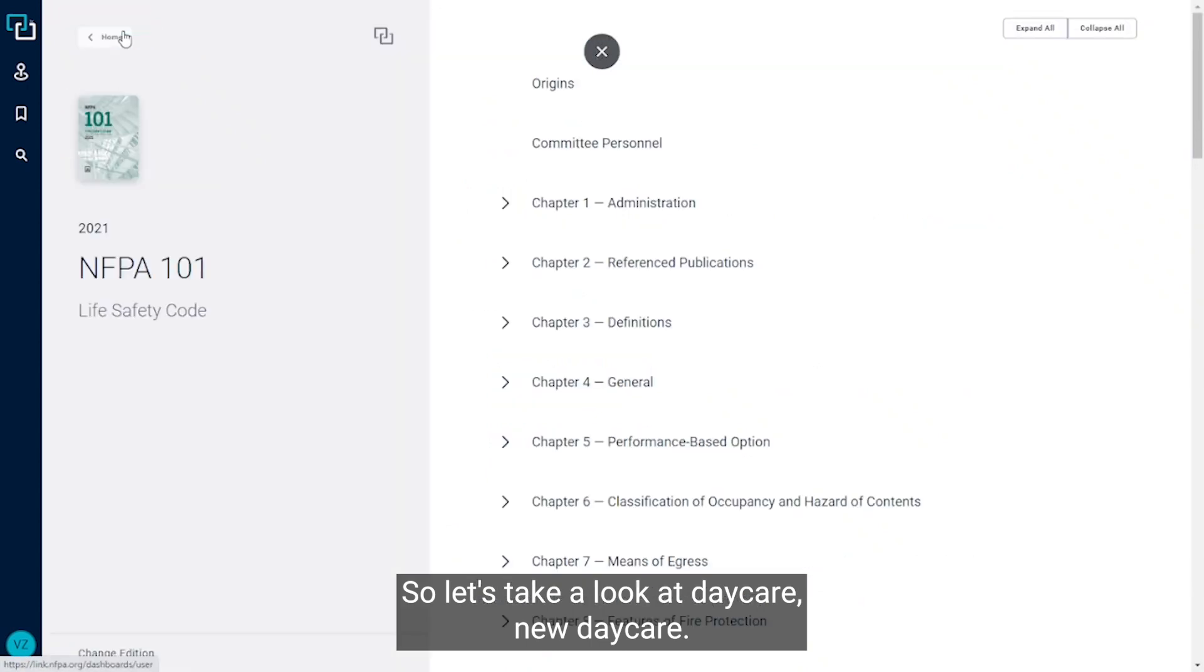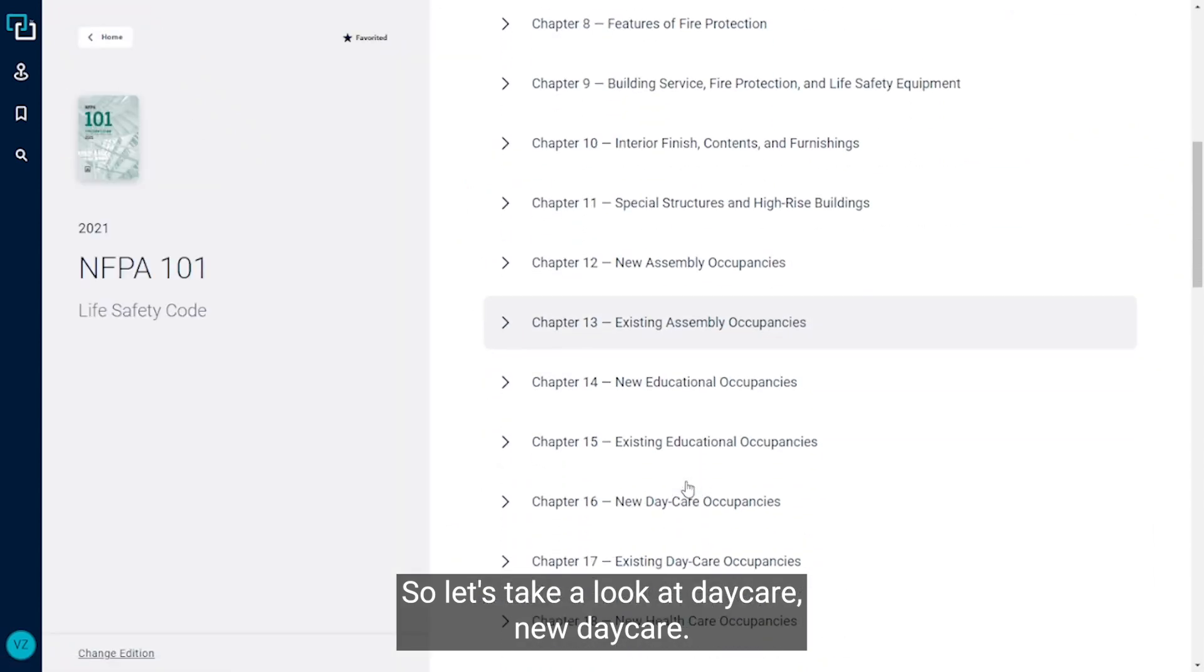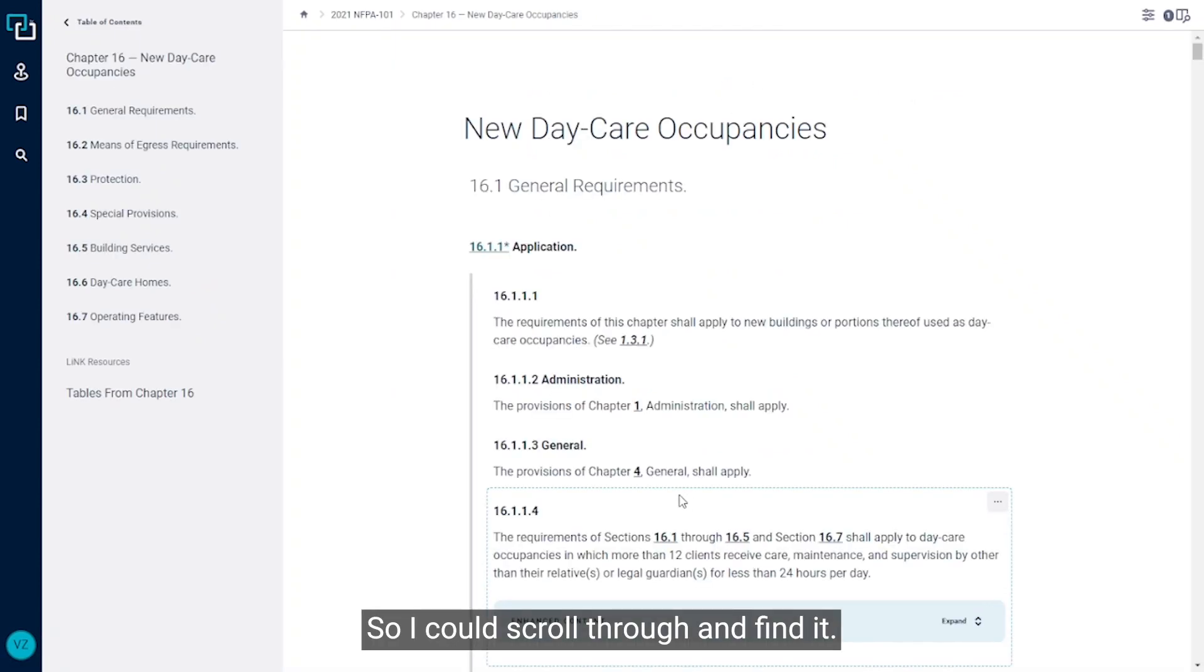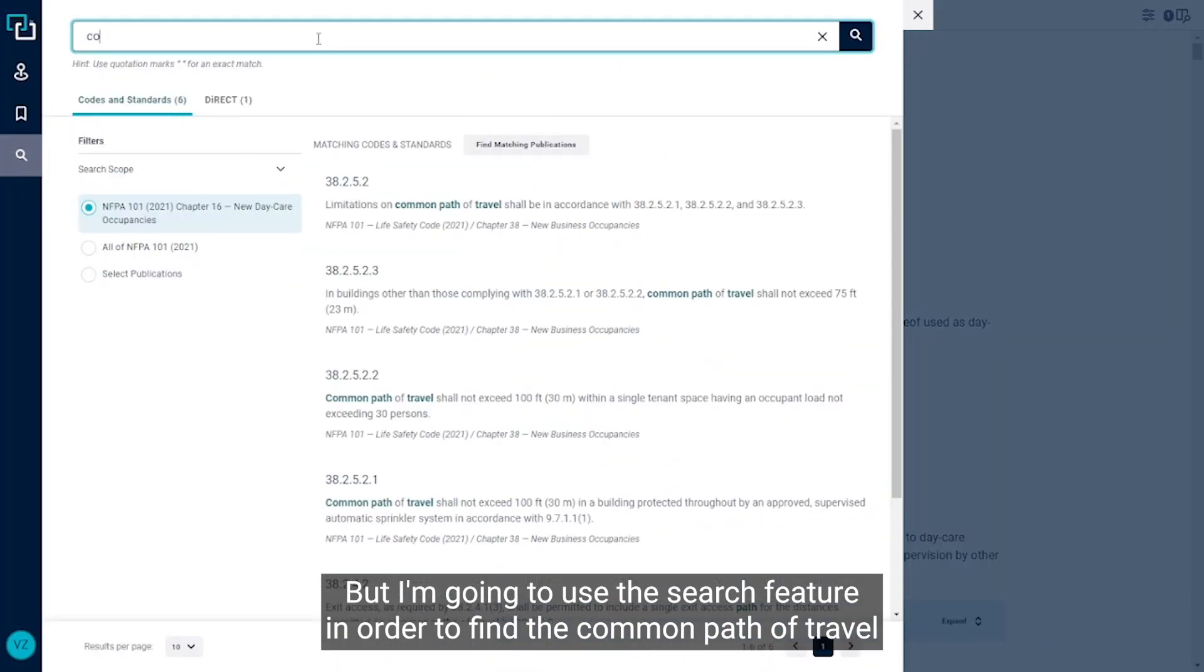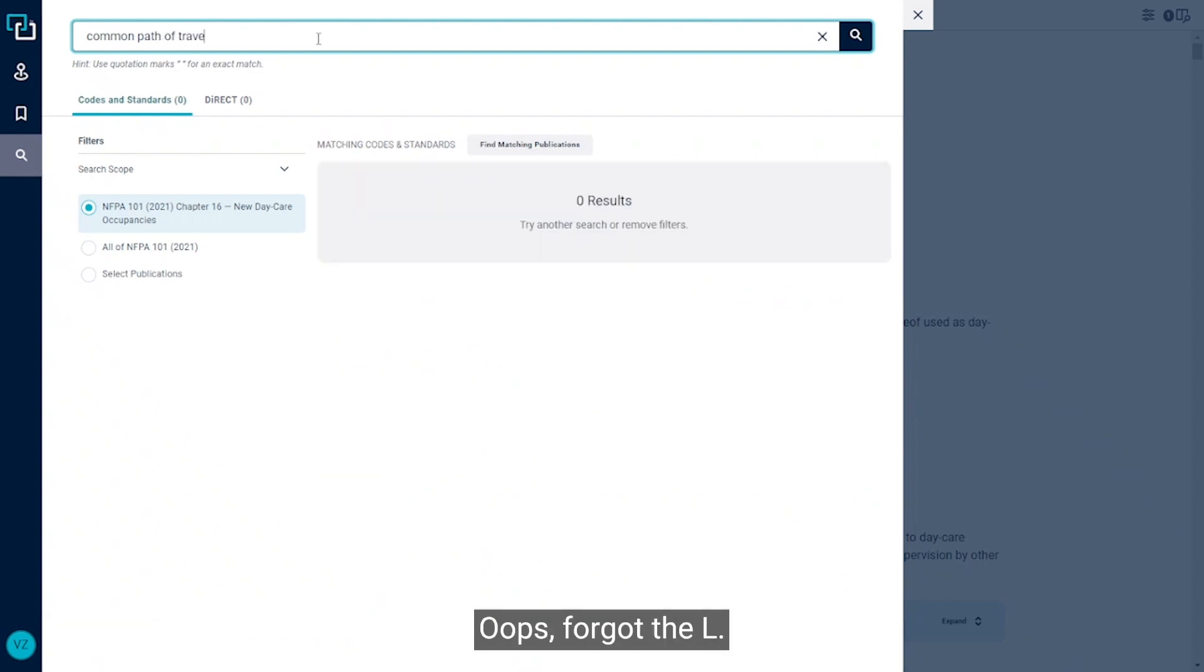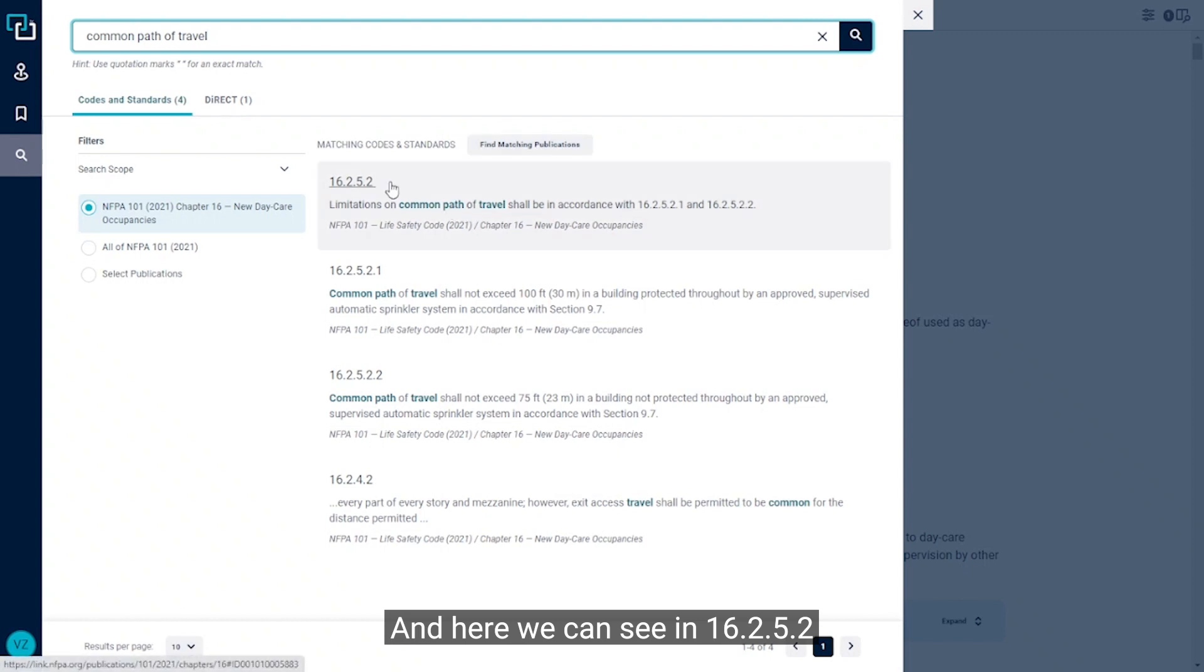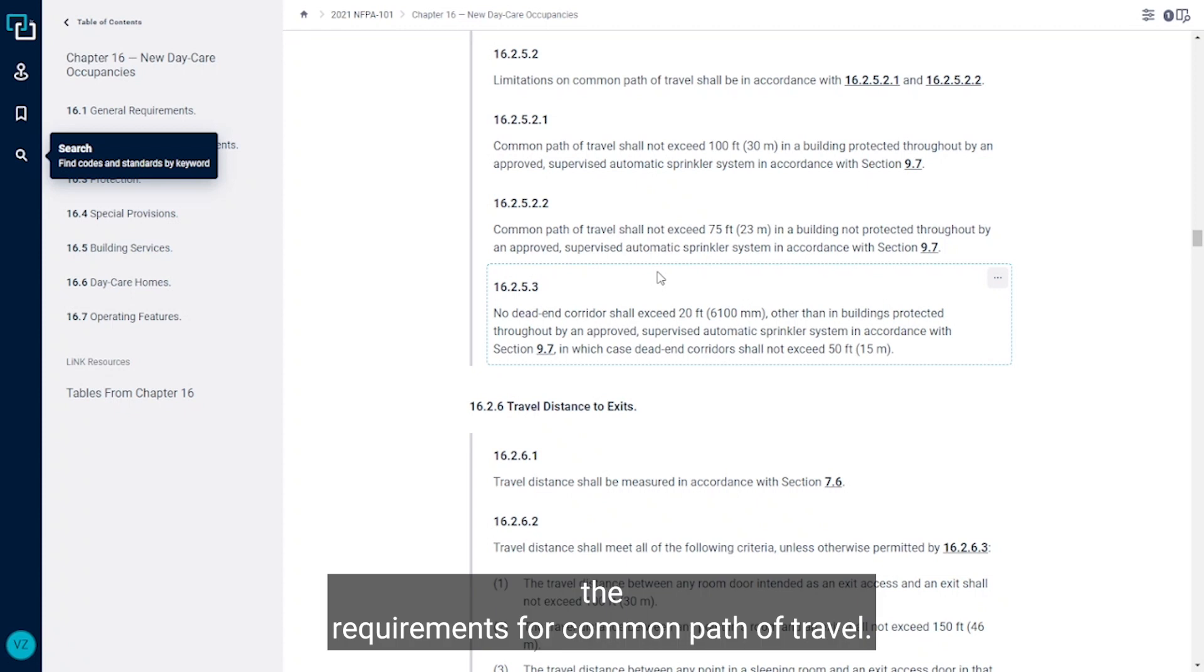So let's take a look at daycare, new daycare. As I mentioned, it's going to depend on your occupancy classification. So I could scroll through and find it, but I'm going to use the search feature in order to find the common path of travel for new daycare occupancies. And here we can see in 16.2.5.2 the requirements for common path of travel.